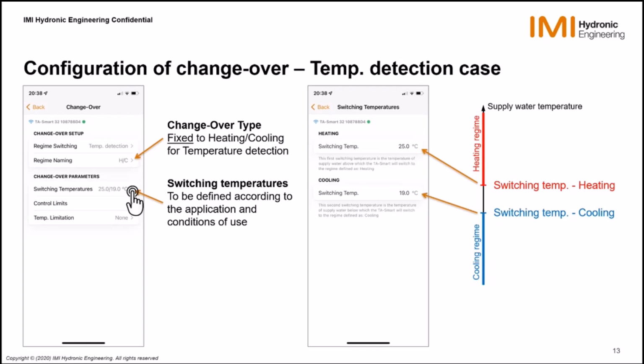Again, here is the idea as I have explained a little bit before. We get two switching temperatures. The water needs to be above that value to go into heating, then it is in heating. If it cools down at some moment, it stays in heating, and it's only when the temperature goes below the switching temperature of cooling that it says that it is cooling.